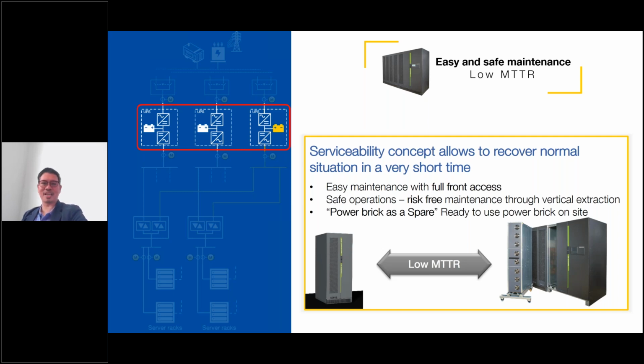Of course, fewer spare parts means faster repair and less cost to the customer. Next year in Asia Pacific, we'll be introducing the maintenance box or maintenance panel shown here. This can be installed in a building where you have multiple UPS units, and you can test the UPS brick in this box, performing 100% internal testing after repair so you're confident the system is running at full capacity. It can also serve as a spare—if you have a 40 module or brick, you can take the spare and insert it to replace the module inside your UPS.